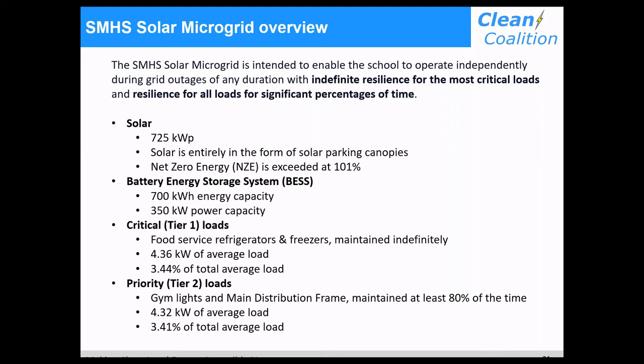The critical loads, the tier 1 loads, are basically the food service refrigerators and freezers, representing an average load of about 4.5 kilowatts, around 3.5% of the total average load. The priority loads, the tier 2 loads, are the gymnasium lights, where staging for disaster recovery and potentially emergency sheltering would occur in the gymnasium and nearby fields.